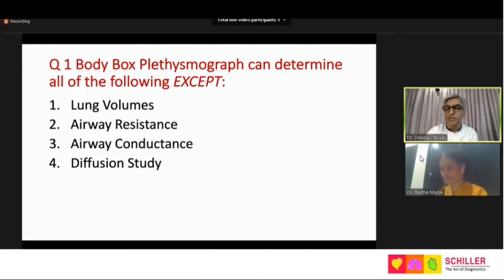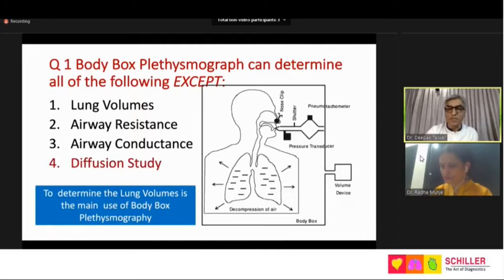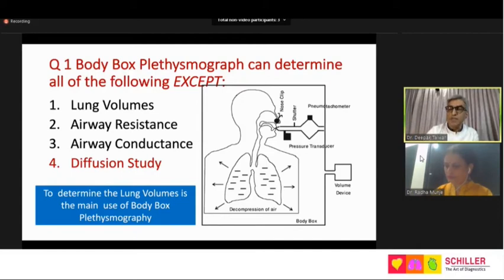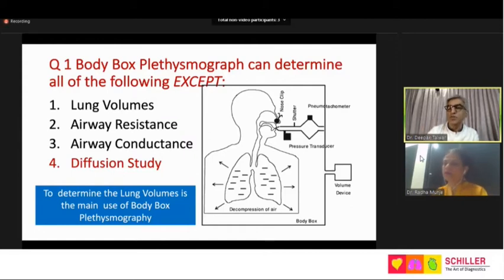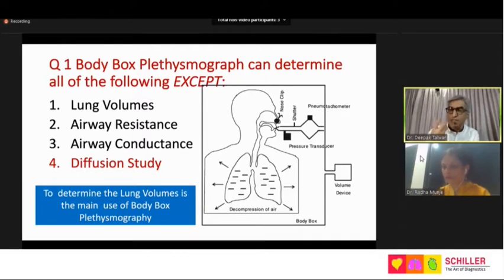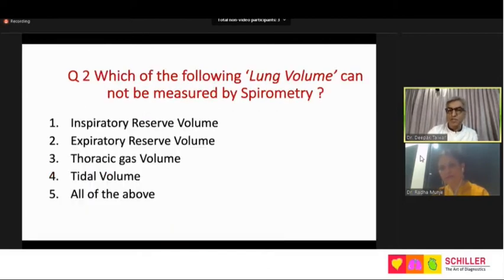The reason we brought this is that in the body box there is a transducer and a shutter; the patient sits in a pressurized cabin whose volume and pressure are known. The volume and pressure of the box versus volume and pressure in the airways and lungs determines the lung volume. Because there is a flow sensor, a pneumotachograph looking at volume, flow, and pressure, it also gives us airway resistance and airway conductance. That brings us to question number two.